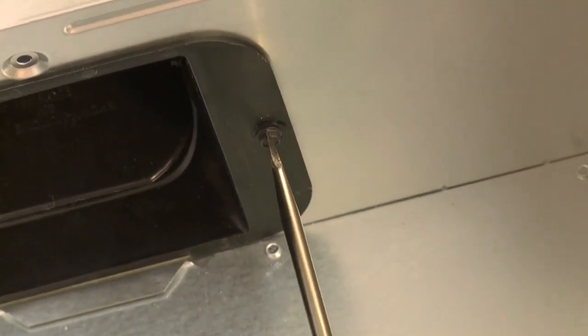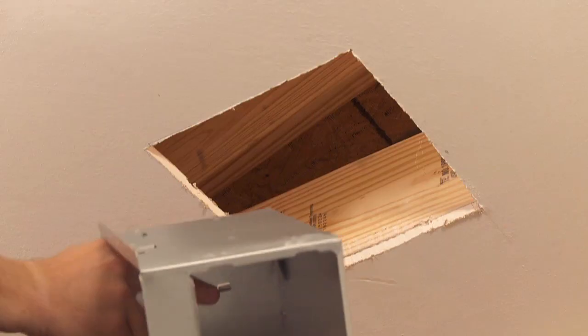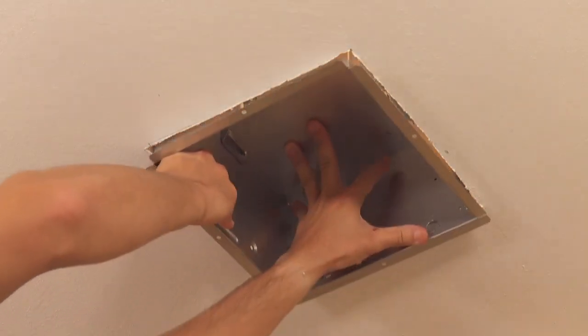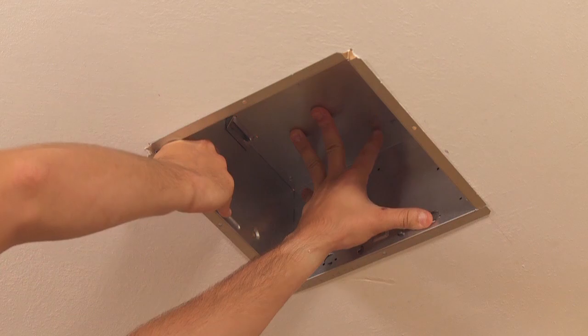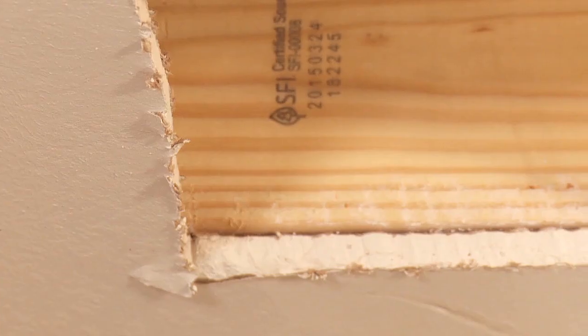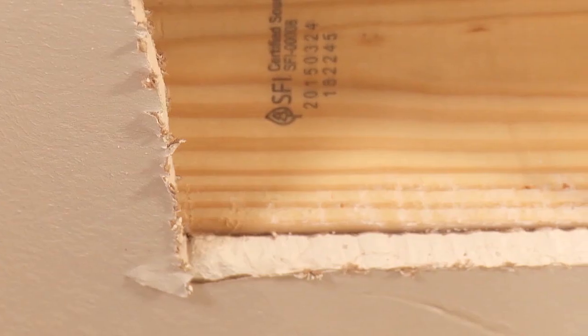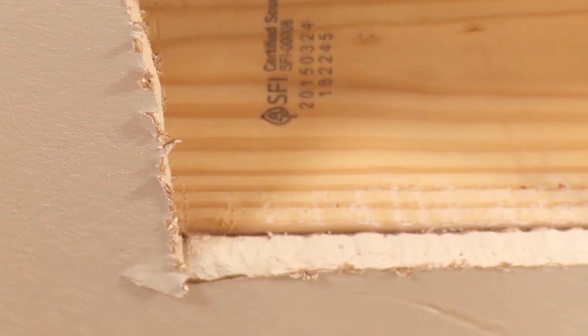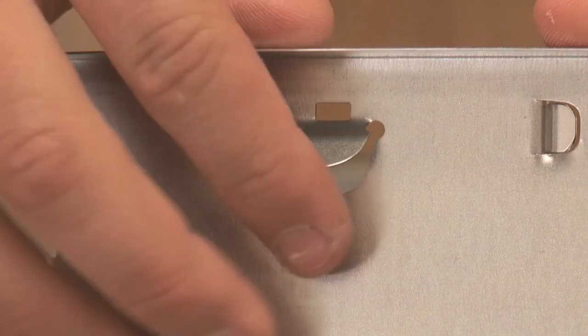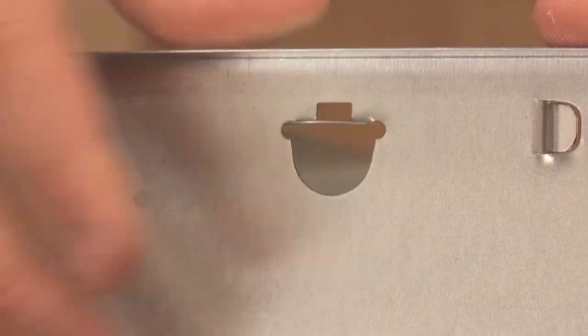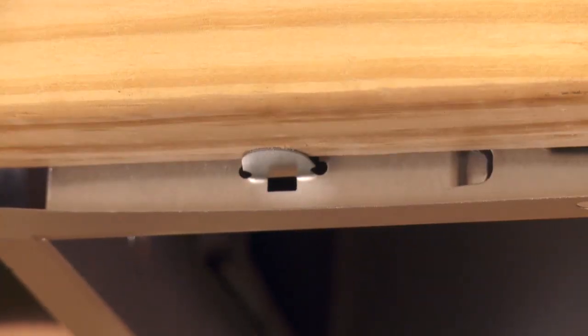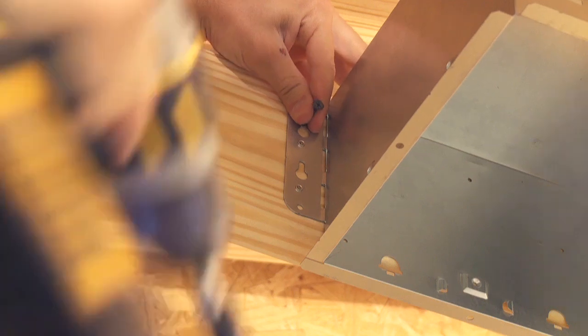When mounting the housing to the ceiling structure, ensure that the bottom of the housing will be flush with the finished ceiling. For proper location, use ½ inch ceiling material. Bend out the housing tabs to fit against the bottom of the structure. Secure the housing through the mounting ears on each side with appropriate fasteners.